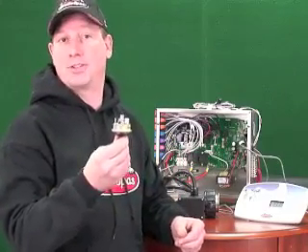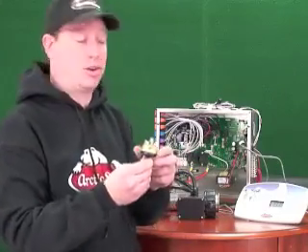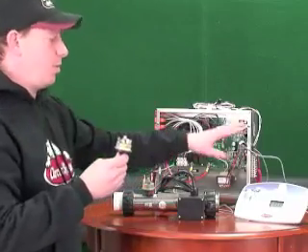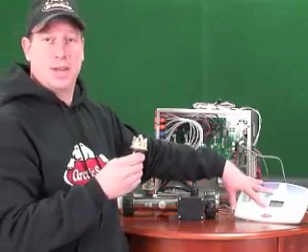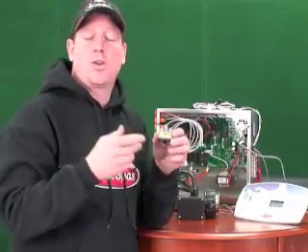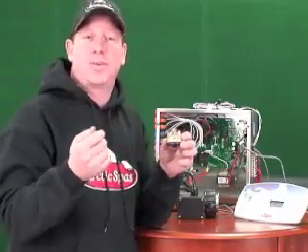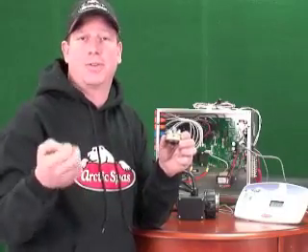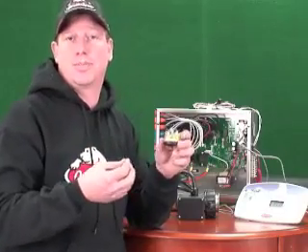We need to understand right off the bat the pressure switch has two error codes. They'll come off your topside display. One error code is FLO, the other one is FLC - flow switch open, flow switch closed.